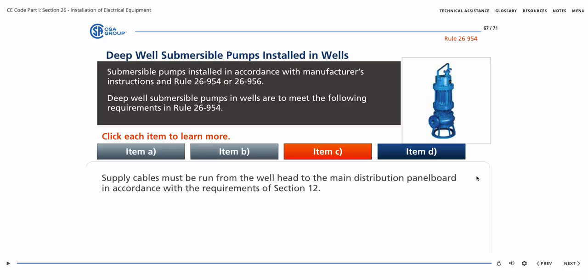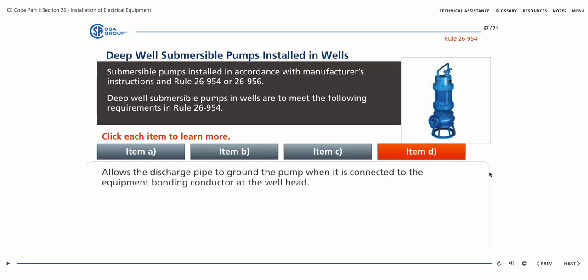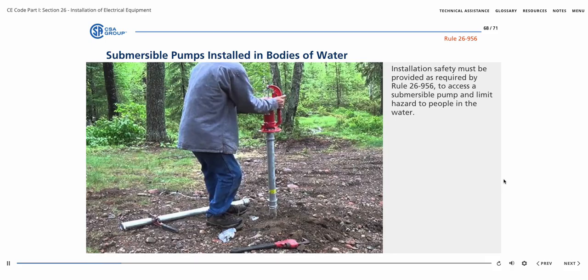Item C requires supply cables to be run from the wellhead to the main distribution panel board in accordance with the requirements of Section 12. Item D allows the discharge pipe to ground the pump when it is connected to the equipment bonding conductor at the wellhead. Installation safety must be provided as required by Rule 26-956 to access a submersible pump and limit hazard to people in the water.